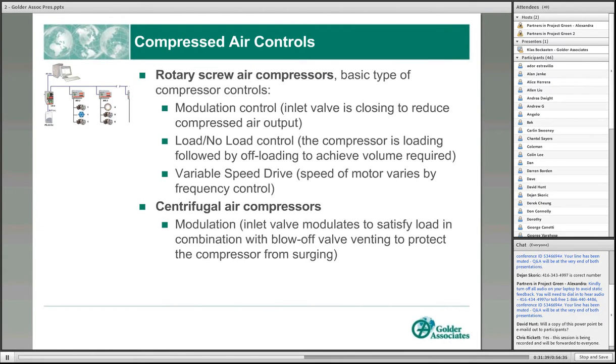Looking at the 2 compressor technologies and the type of controls that you can effectively modulate the compressor, because the compressor will not always be discharging at full load. The most common systems are modulation control, followed by load, no load. And we see more today a variable frequency drive on the compressor, allowing you to slow down the motor and more cost effectively deliver compressed air at part load.